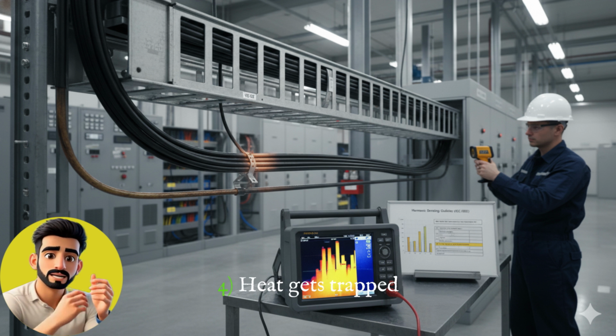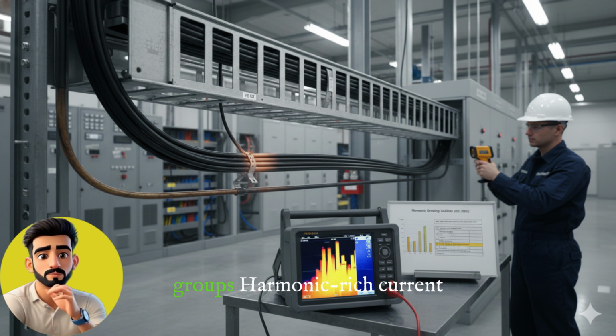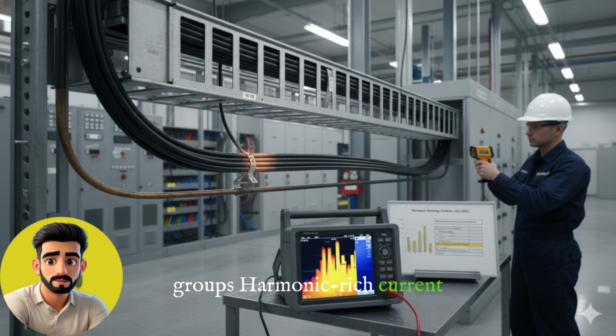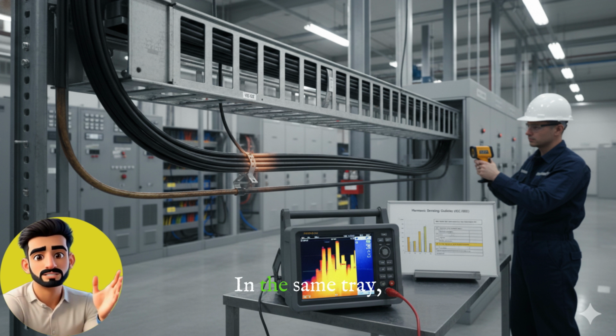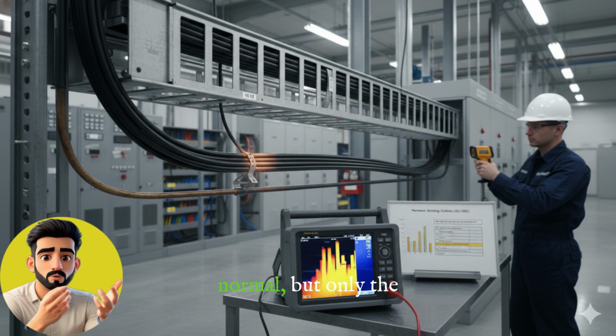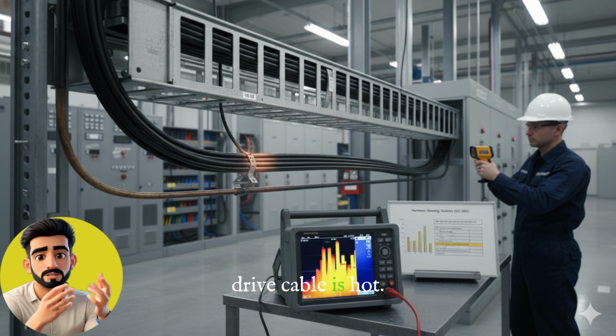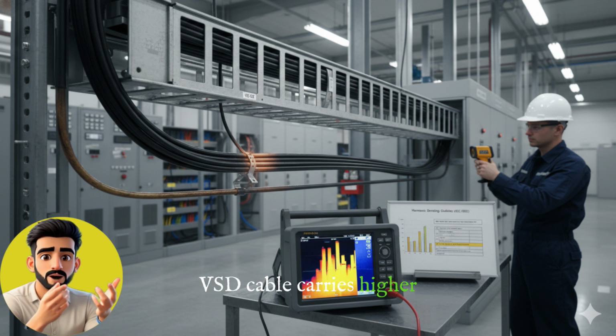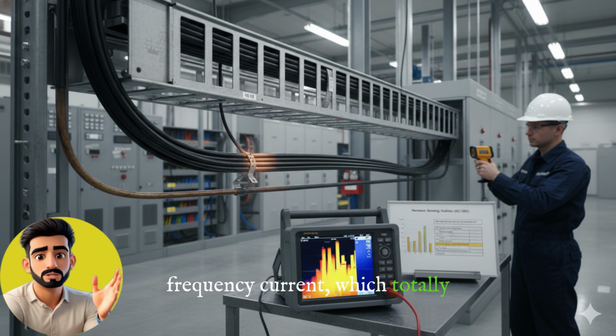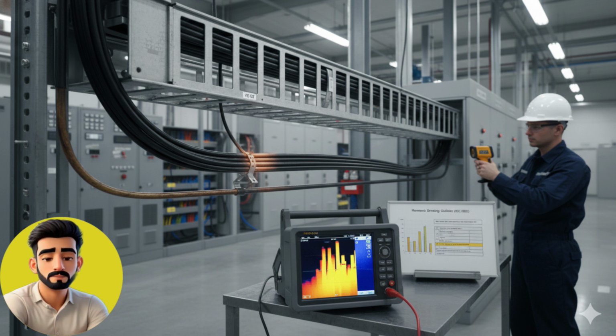4. Heat gets trapped in cable trays and groups. Harmonic-rich current does not only produce heat, but also traps heat. You might have seen, in the same tray, all healthy cables are normal, but only the drive cable is hot. The reason is clear. The VSD cable carries higher frequency current, which totally changes heat transfer behavior.